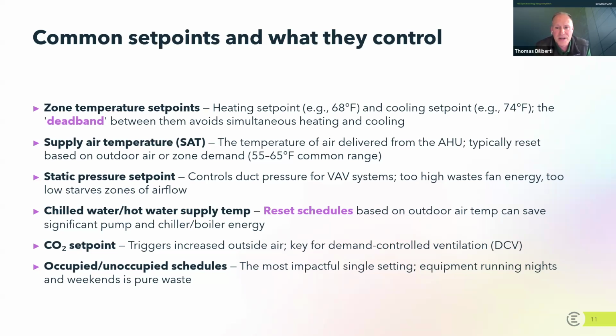Let's suppose also in this scenario that the sun comes up above the horizon, occupants come in the building, heat loads start to grow. And so now the temperature in the building becomes 70 degrees or 72 degrees or 74 degrees. And it's not the heating system that's driving that change any longer. It's all the heat sources within the building. And let's suppose it gets up to 74 and even beyond 74 degrees. And now the building has the ability to cool. So its cooling set point is 74. And if the building gets up to 76 degrees, then the building is going to want to cool itself back down to 74. That long-winded explanation allows me to describe what the dead band is.